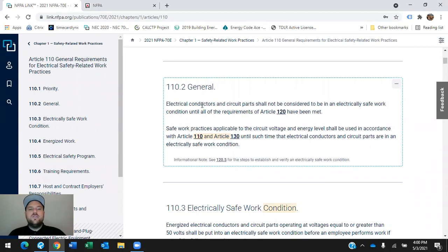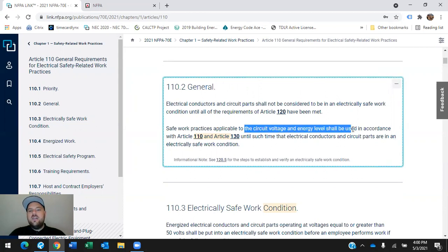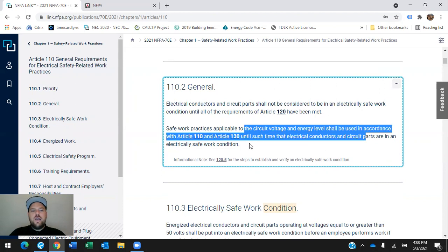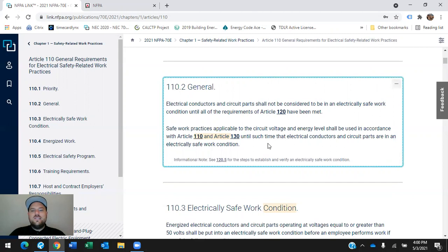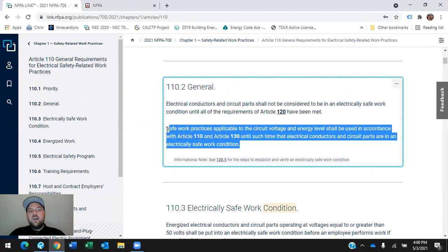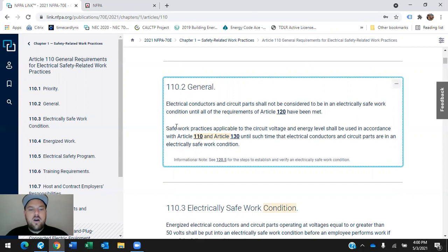110.2, general. Electrical conductors and circuit parts shall not be considered to be in an electrically safe work condition until all of the requirements of Article 120 have been met. Safe work practices applicable to the circuit voltage and energy level shall be, again, look at that, shall be used. That's what we're talking about. This is mandatory. Safe work practices applicable to the circuit voltage and energy level shall be used in accordance with Article 110 and 130 until such time that electrical conductors and circuit parts are in an electrically safe working condition. That could be that they are locked out and tagged out, right? That could be that they're completely demoed out. Whatever it is, we need to follow what this is saying in all three articles, 120, 110, and 130.